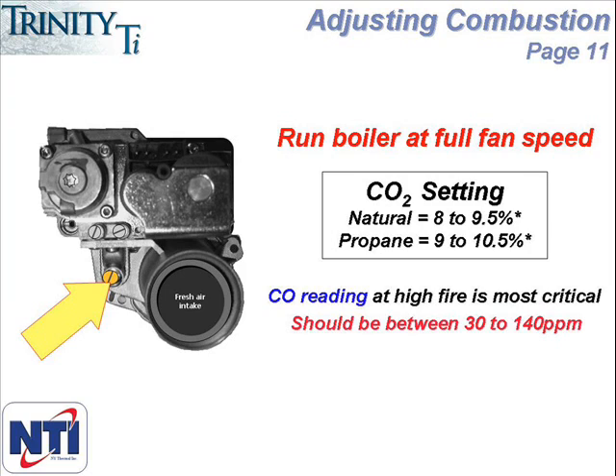If the CO2 reading is too low, increasing the amount of gas by turning the input screw counter-clockwise will increase the CO2 number. Slowly turn the input screw until the CO2 reading settles at 9%.